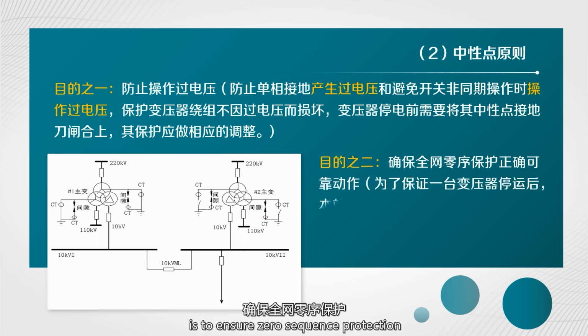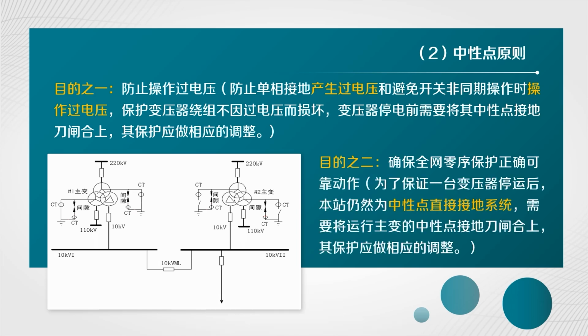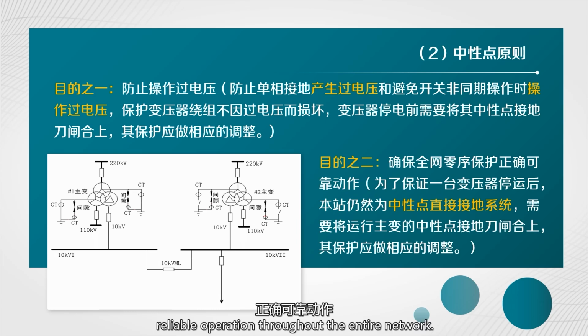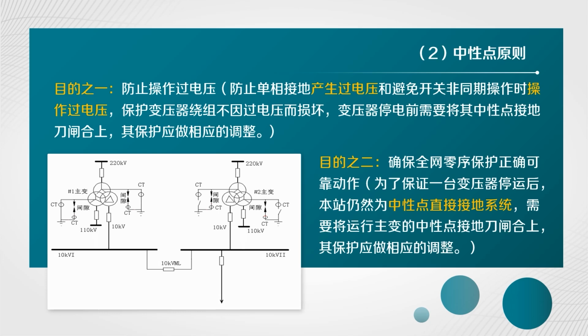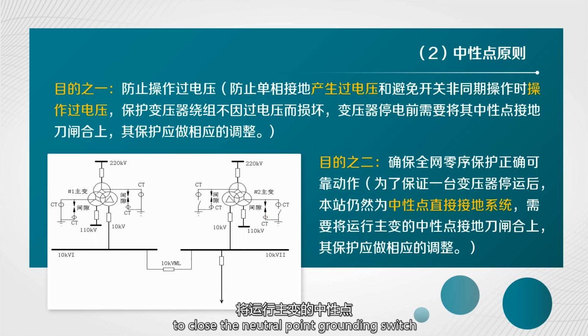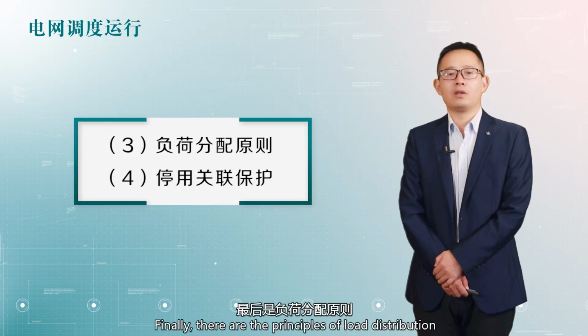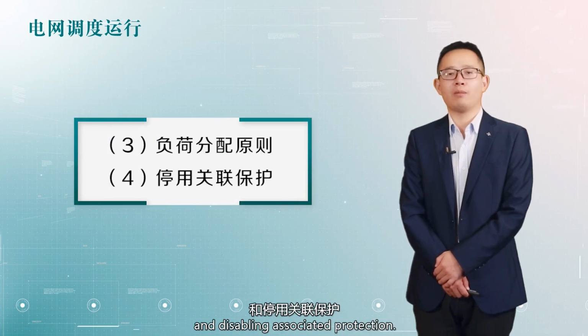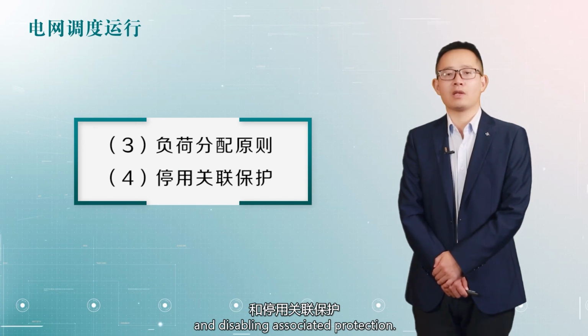The second purpose is to ensure zero sequence protection operates correctly and reliably throughout the entire network. In order to ensure that after a transformer is shut down, the station is still a neutral, direct grounding system, it is necessary to close the neutral point grounding switch of the operating main transformer, and its protection should be adjusted accordingly. Finally, there are the principles of load distribution and disabling associated protection.